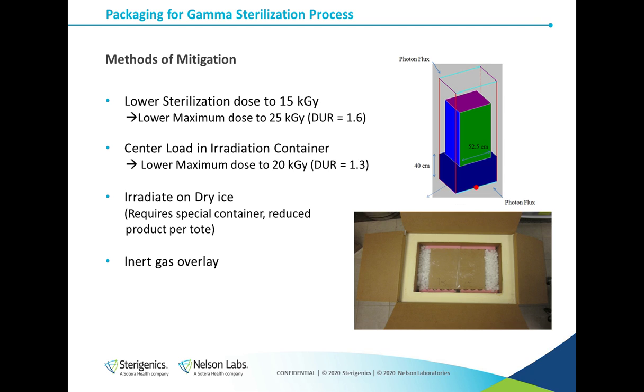One way is to maybe just lower our minimum sterilization dose to 15 kilogray. If we lower our sterilization dose to 15 kilogray, we can also lower our maximum dose because we know we can maintain a dose uniformity ratio of 1.6. So if we're able to lower our sterilization dose by revalidating our sterilization dose to 15, we can also lower our maximum dose to 25. So that may result in a better product after irradiation.